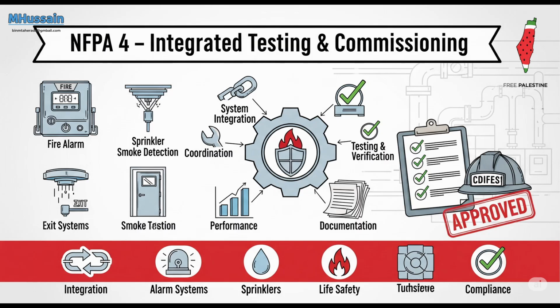Back in 2011, they approved separating it out, giving it its own document, NFPA 4. And then in 2018, it officially became a mandatory standard. Wow. So that's a huge shift from nice to have to must do. Monumental, really. It means integrated testing is now a mandatory requirement, not just a friendly suggestion. It fundamentally changes the landscape of fire and life safety. So our mission today is to unpack what this critical shift means for fire and life safety in the spaces you inhabit every single day, your office, your apartment building, everywhere.